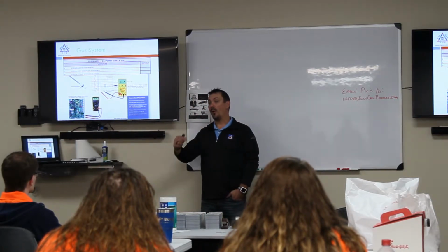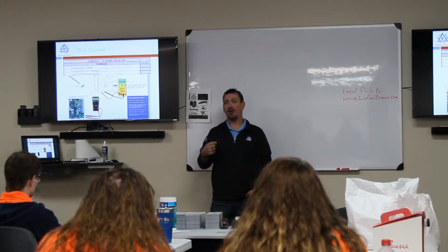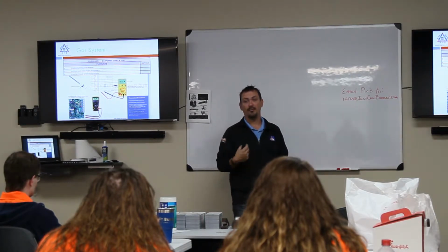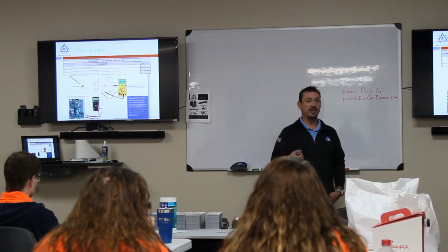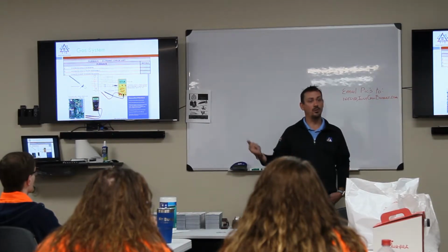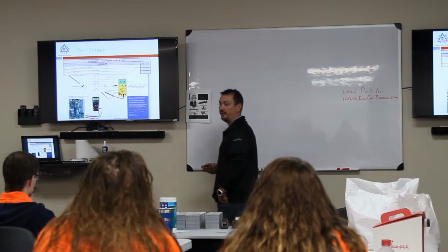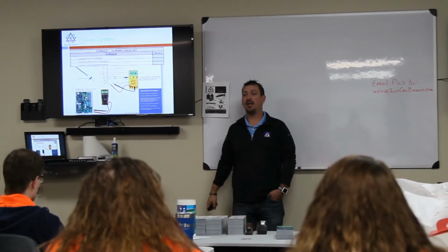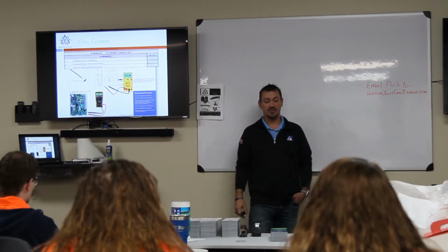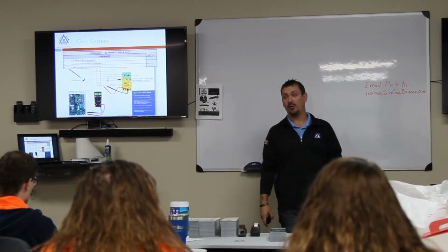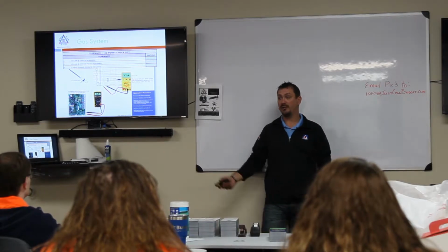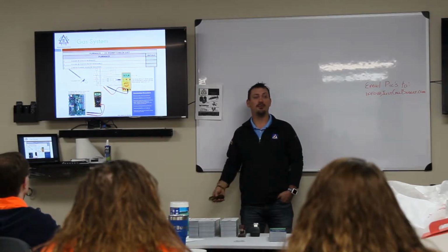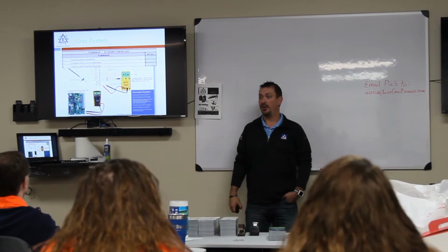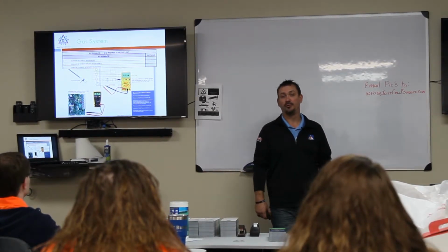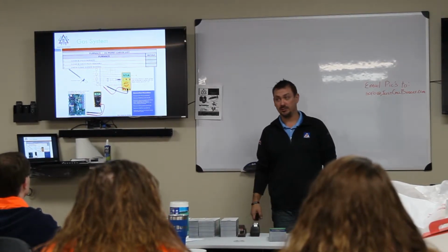So that's at 0.1 or less. At 1.5, you're going to get that rapid amber flash. So if you come up to a unit and you're seeing that rapid amber flash, you can definitely clean that flame sensor and see how well you improved it, see if it got up into the 3s or the upper 2s. At that point in time, if you'd like to leave that flame sensor, you can. Otherwise, it would be a good time and a suggestion to offer that homeowner a new flame sensor. They're cheap enough, and that's a component that we don't want to have to come back after we did a clean and check when it's 20 degrees because we couldn't improve the reading or the rating on that flame sensor.